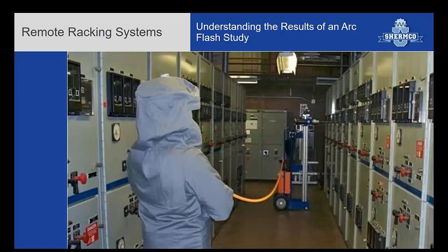Another item, because racking breakers can be so dangerous: once again, if you can get outside the arc flash zone, anything you can do to that is a really big help. So there's remote racking. Typically, you can get far enough out of the zone. You want a good solid device. There are several companies that make them that understand not over-torquing the breaker. But remote racking is a very good thing to help, especially on those cases where you have this real high incident energy on the incoming side of the transformer. There's not a whole lot maybe you can do, but the only task typically you're doing is racking that breaker in and out. So this might be a good solution to get around that common problem.